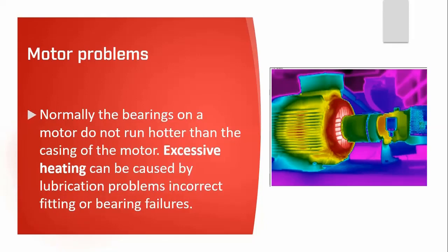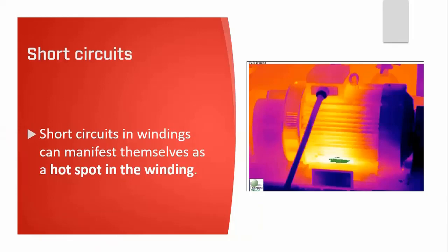Short circuits in windings: motor insulation is classified as A, B, F, etc. according to the ability to resist aging and failure due to heat. When operated normally at maximum authorized temperature, average motor life is around 20,000 hours. As a rule of thumb, for each 10°C below the rated temperature the life will double, and for each 10°C above, the life will be halved. Other factors also affect temperature and motor life.